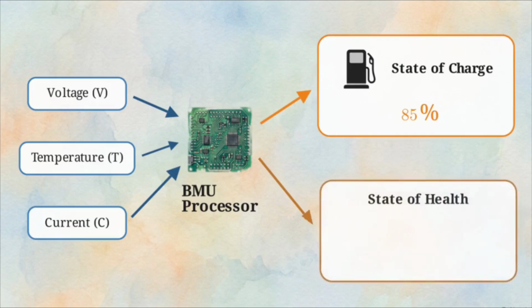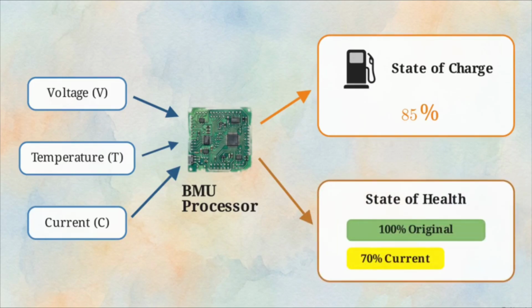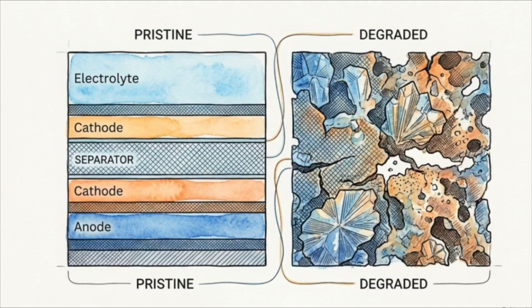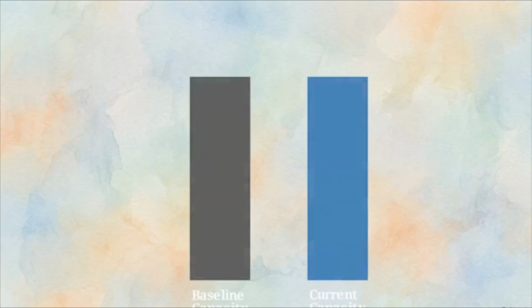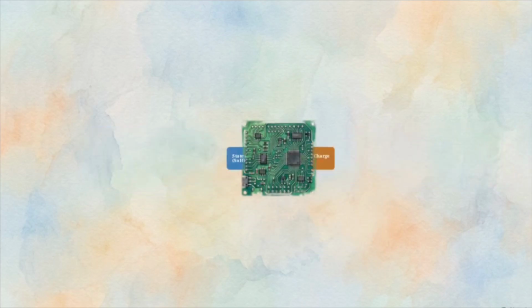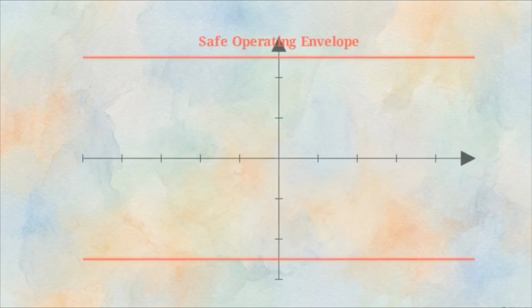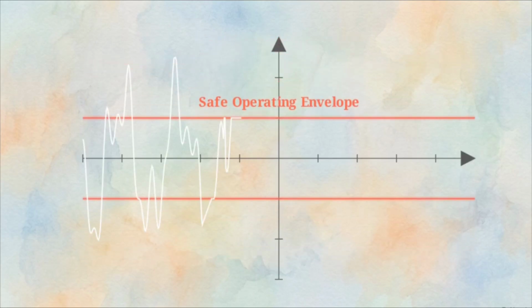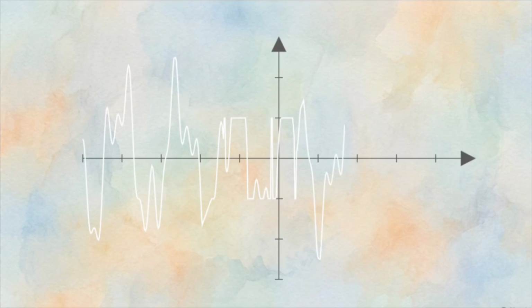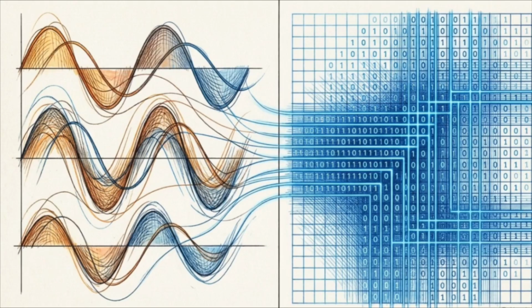Simultaneously, it calculates a second output, the state of health. Over its lifetime, the internal chemistry of a battery degrades. The state of health algorithm tracks this degradation by comparing the pack's current storage capacity against its original baseline capacity when brand new. By cross-referencing the state of charge against the degraded state of health, the BMU continuously calculates a dynamic, safe operating envelope, setting hard mathematical limits on current flow in real time. The BMU serves as the translation layer, converting raw analog sensor readings into precise digital constraints.